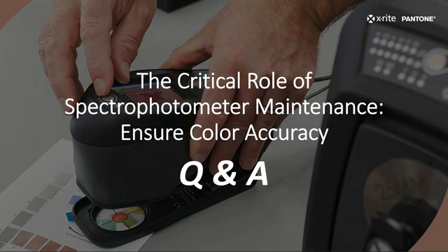One of the things to remember with NetProfiler is that it's going to correct the instrument for whatever state it was in at the time you ran NetProfiler. So worst case scenario, you have a device that's drifting drastically, and you correct it with NetProfiler, but a day or two later, it's drifted again, even further away. That's an extreme case, but I use it as an example to help understand the difference between NetProfiler and certification. The best way to maintain an instrument is using both, of course. Let NetProfiler account for any of those minor drifts that are happening over time, because if you only did annual certification, then you're only going to know 12 months later if your instrument is still measuring right. If something happened in that 12-month period between certification one and certification two, you will have missed something that caused your instrument to start reading differently somewhere in the middle. And how do you go back now and deal with that?